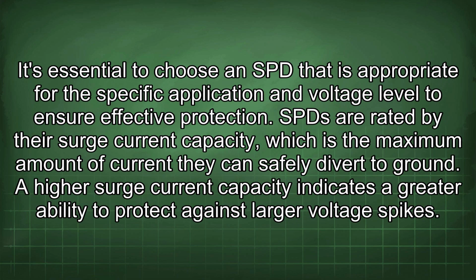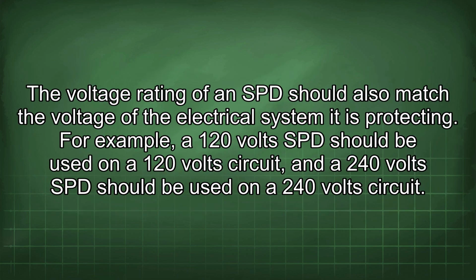It's essential to choose an SPD that is appropriate for the specific application and voltage level to ensure effective protection. SPD are rated by their surge current capacity, which is the maximum amount of current they can safely divert to ground. A higher surge current capacity indicates a greater ability to protect against larger voltage spikes. The voltage rating of an SPD should also match the voltage of the electrical system it is protecting. For example, a 120 volt SPD should be used on a 120 volt circuit, and a 240 volt SPD should be used on a 240 volt circuit.